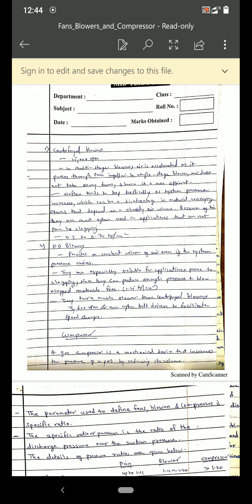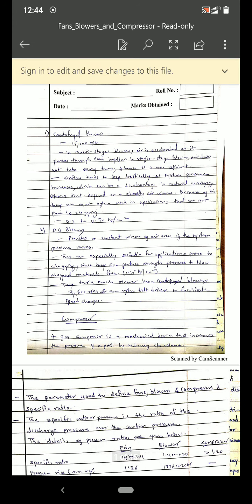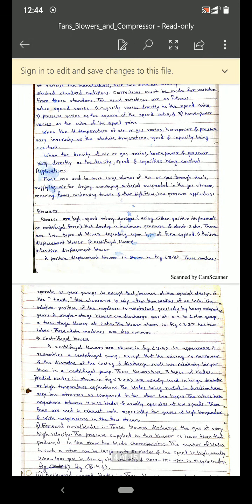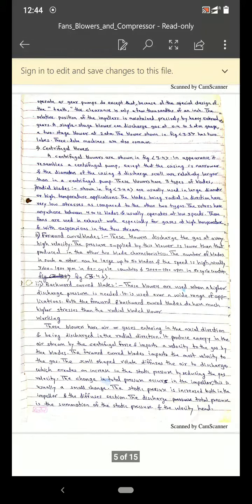The discharge pressure of a centrifugal blower is between 0.3 to 0.70 kg per centimeter square, and for a positive displacement blower it is 1.25 kg per centimeter square. Centrifugal blowers are generally not used where clogging of the pipes takes place, whereas positive displacement blowers can be used in pipelines where clogging occurs.